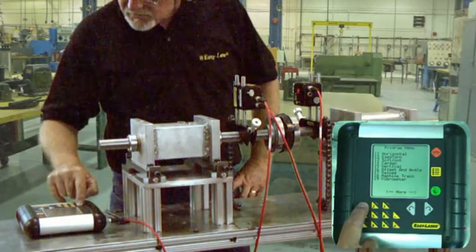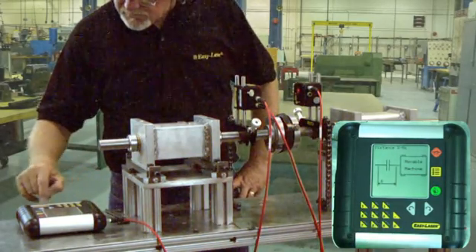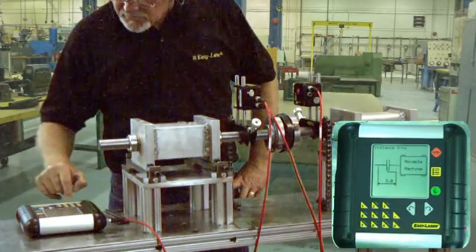Here we will do a horizontal alignment using program 11 with the coupling attached. The program prompts us to input the tape measurements. Since we have already taken them, we can input the distance S to M as 6 inches.